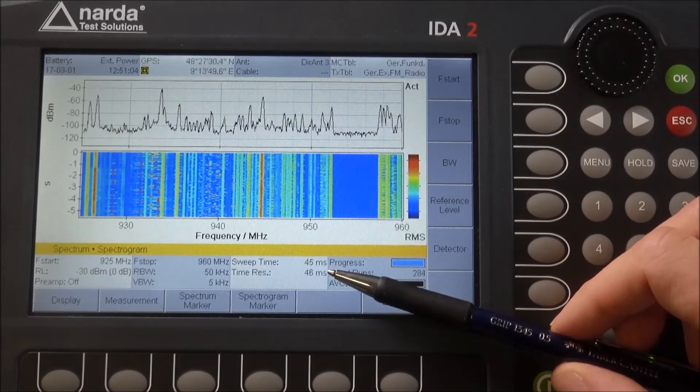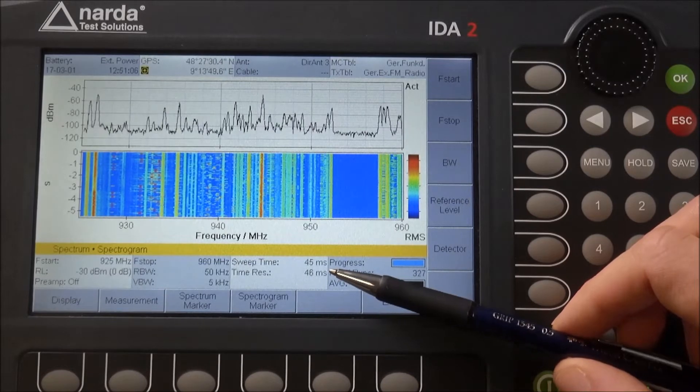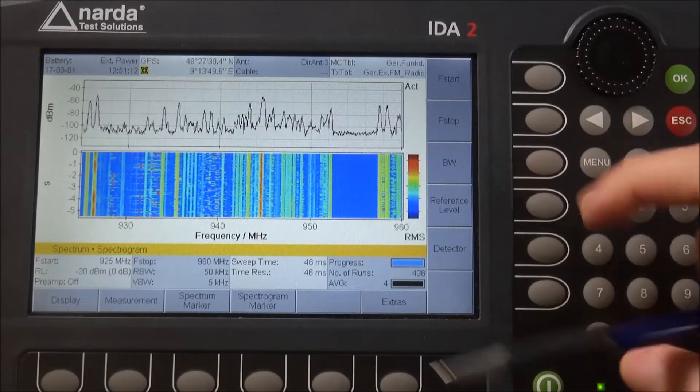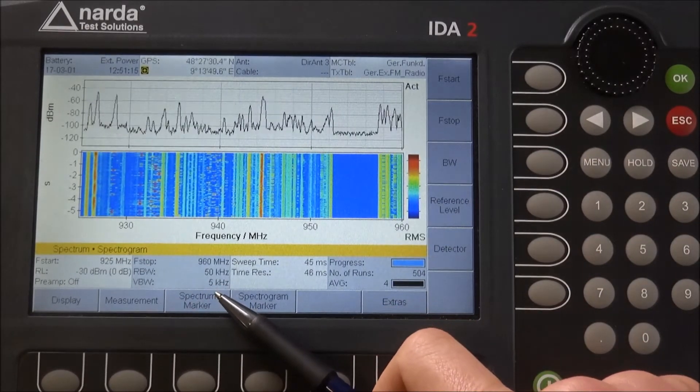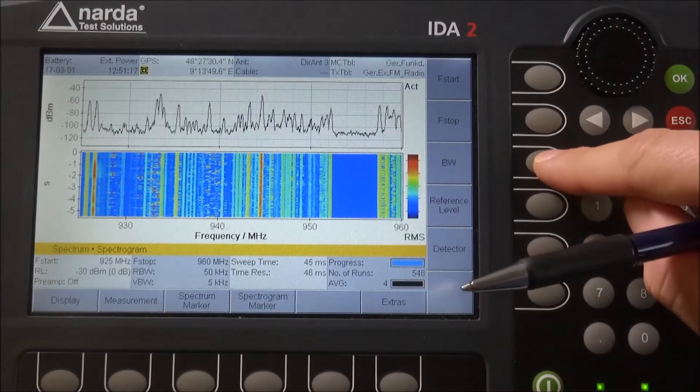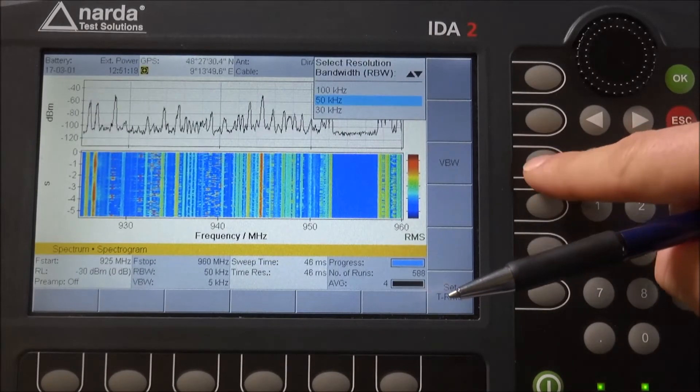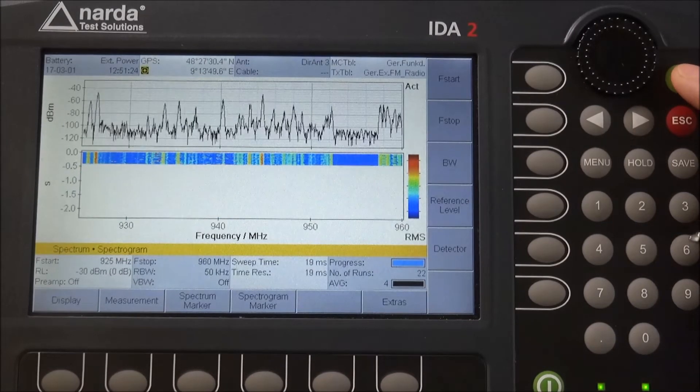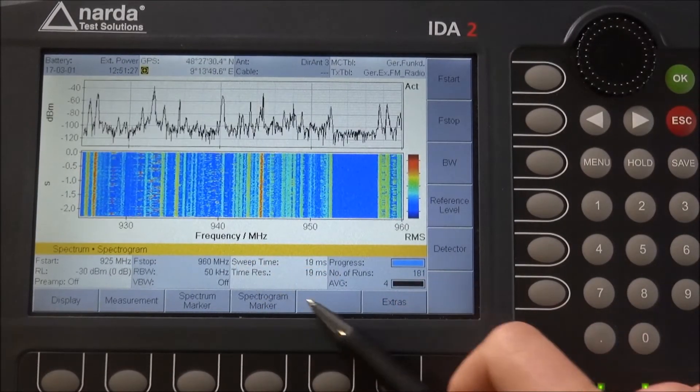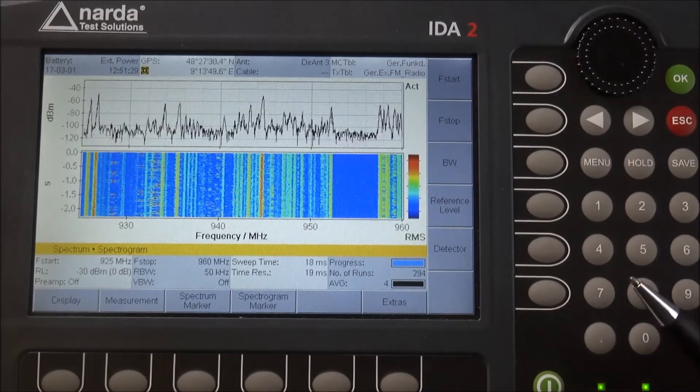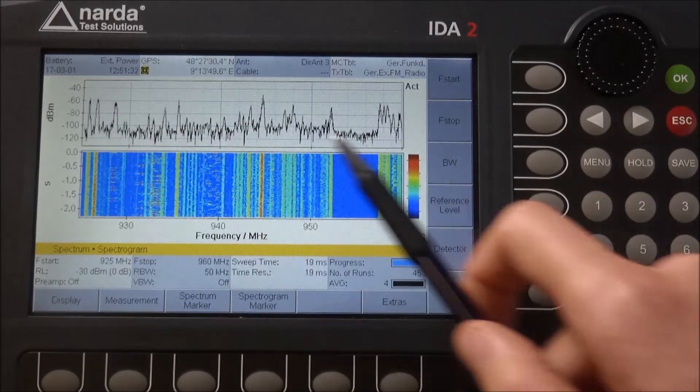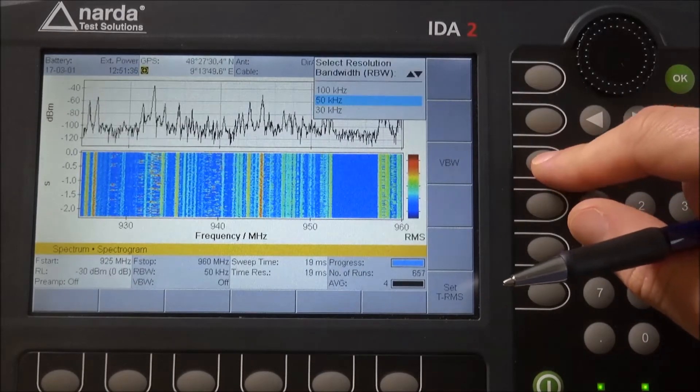To further decrease the sweep time and increase our signal detection chance, we can switch off the video filter, which is now at five kilohertz. Click on bandwidth, then VBW, and switch the filter off to improve sweep time even more. Now you can see the noise floor looks more noisy, so I typically like to use slight video filtering.